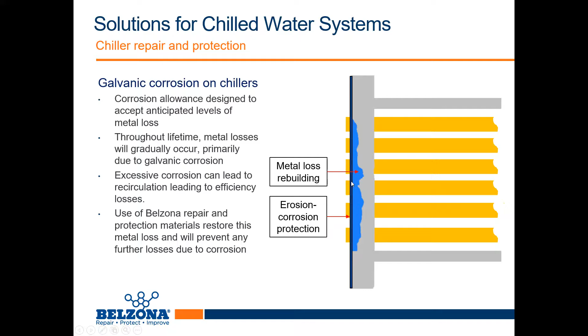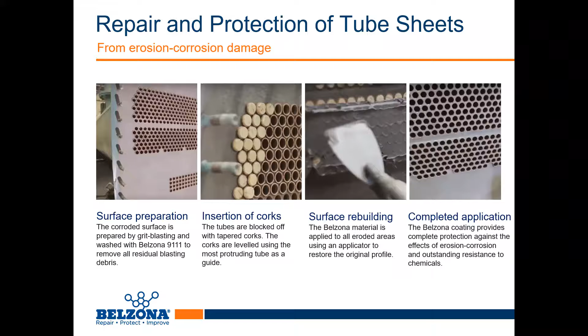And then put on some erosion corrosion protection, a final coated layer. Now this is achieved, as you can see, we have to get surface prep, as that is everything. So what we're going to do is put some corks inside your tubes to prevent it from getting any media in it while we're blasting. Once we achieve the proper surface, we're going to rebuild with our paste grades, as you can see right here. And we will rebuild this typically up to where the tubes are sticking out. So you're going to get that extra layer of sacrificial metal in there. And then a complete application is always going to be to coat and protect the repair, as well as give you that long-term protection.